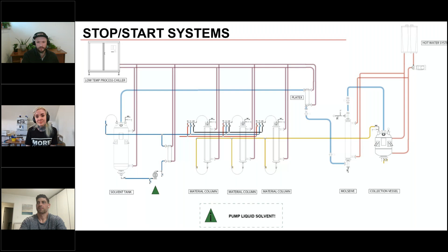The next bottleneck that we see a ton of is improper heater and chiller sizing. Almost everywhere we go, there is ineffective, like undersized heating or undersized cooling. And so when we look at why that's important and where that is, just to cover it, you have heat going into your collection pot. You're typically sending 40 degrees Celsius. Sorry, I don't know that in Fahrenheit.